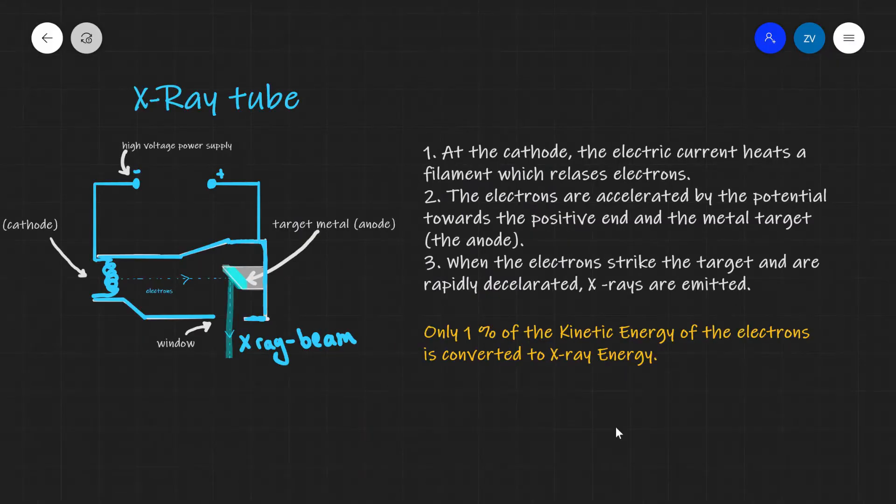Now let's summarize what we have just said. Once again, at the cathode, also known as the heater, the electric current heats a filament. This releases electrons. The electrons are then accelerated towards the target metal, the anode. They're accelerated by the potential towards the positive end. And when the electrons strike the target, they're rapidly decelerated, they rapidly lose energy and x-rays are emitted.